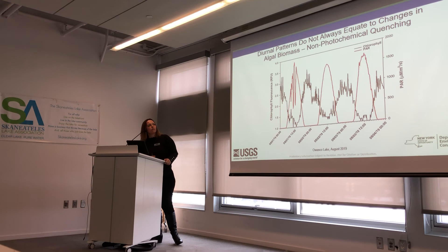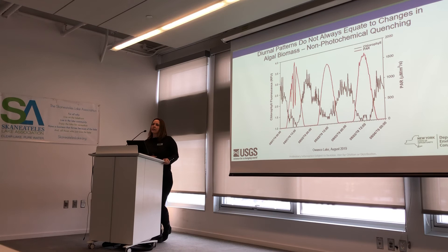Just because you see diurnal variability does not necessarily mean your algal biomass is changing. Here the black line is chlorophyll fluorescence and red is light intensity — you can see a pretty nice inverse relationship there. Our fluorescent sensors do have value and utility, but we need to be cautious in how we interpret those data and look at patterns over time and with respect to other data.